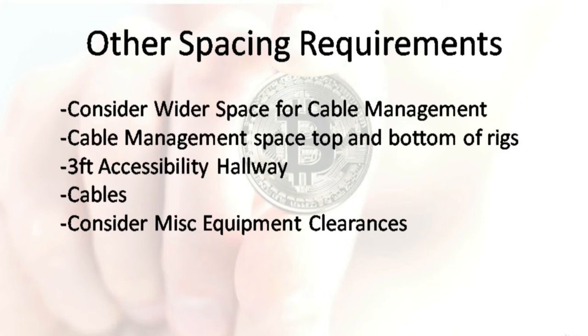So be sure not to jam-pack all of your rigs together with no spacing between them when you are calculating how many rigs you can have within a cabinet or a rack. Now, I would also recommend leaving at least 3 feet between the rows of cabinets or racks to allow accessibility for maintenance as well as to optimize airflow.